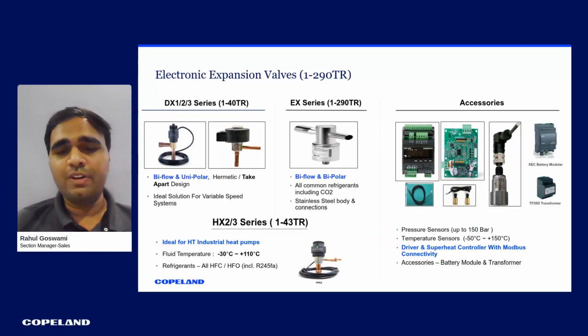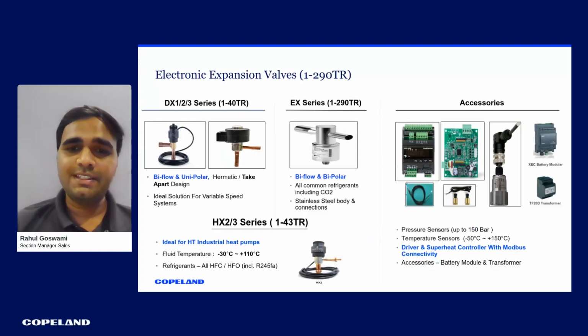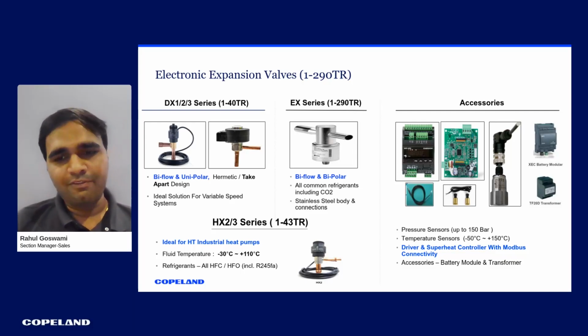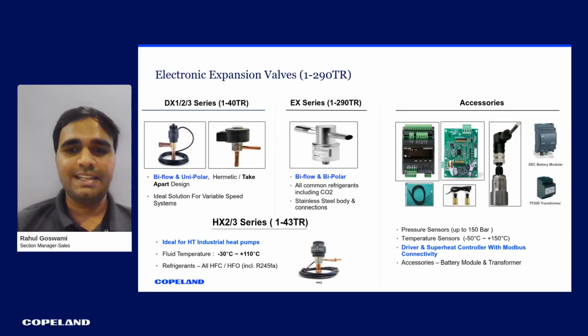Coming down to the electronic expansion valves, we have different series available. First is DX series, which caters up to 40 TR of solution. Again, this is a biflow and unipolar expansion valve, and it is very ideal for your variable speed requirement, inverter technology. And then we have EX series. This EX series can cover up to 290 TR capacity. This is also biflow and bipolar. All common refrigerants are covered, and even CO2 application is also covered in this EX series.